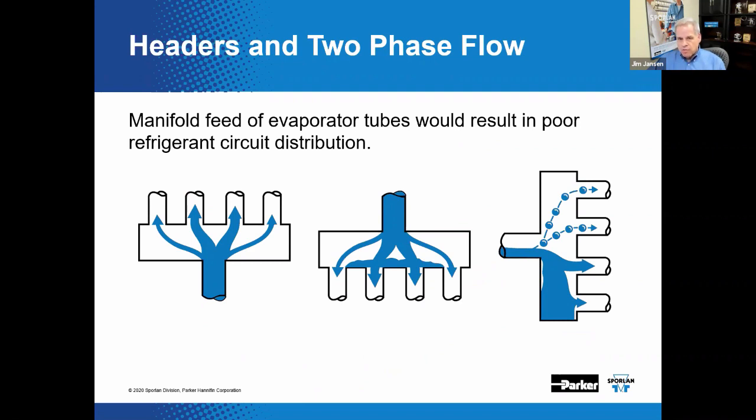If a simple header is used to divide the flow into each of the evaporator circuits, those circuits will not receive the same equal amounts of refrigerant from a phase perspective. Gravity and friction come into play and the lower circuits of the evaporator will invariably receive the most liquid, resulting in hunting or flooding problems, while the upper circuits will likely be starved for refrigerant, reducing the effectiveness of the evaporator. For single-phase flow, a header assembly works just fine, but feeding the evaporator is not one of those places.